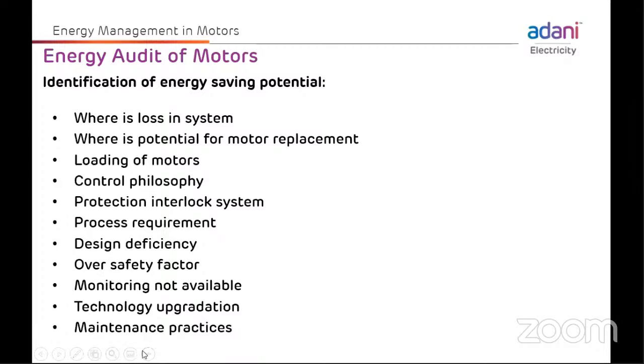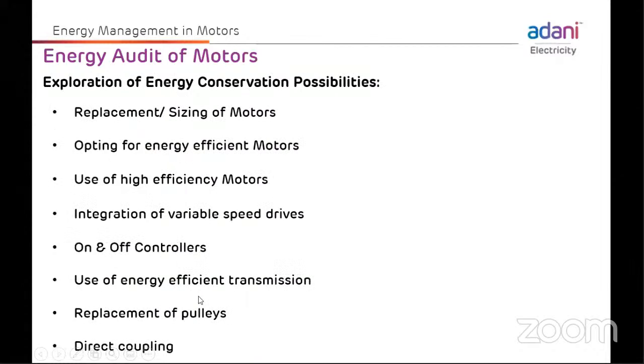Once you find out the losses, we can find out the possibilities to overcome them - like replacement, sizing of motors, optimal use of energy efficient motors, use of high efficiency motors, integration of variable speed drives. If there is no process requirement, we can reduce the speed drive, change the on-off control, use energy efficient transmission, replace pulley and coupling systems, change gear coupling or hydraulic coupling to direct coupling.